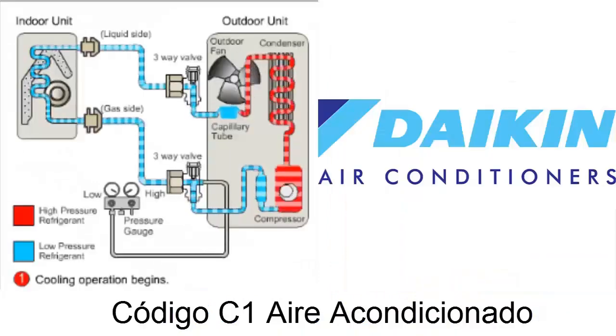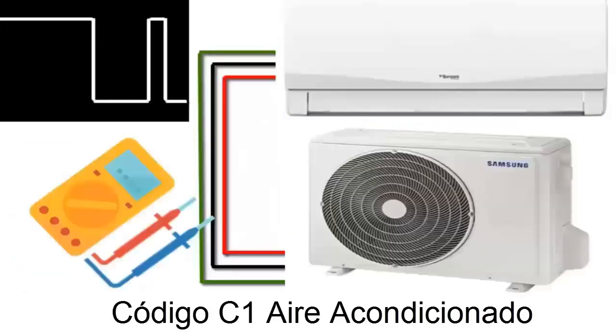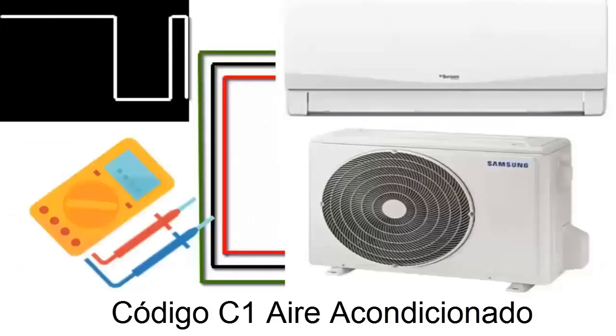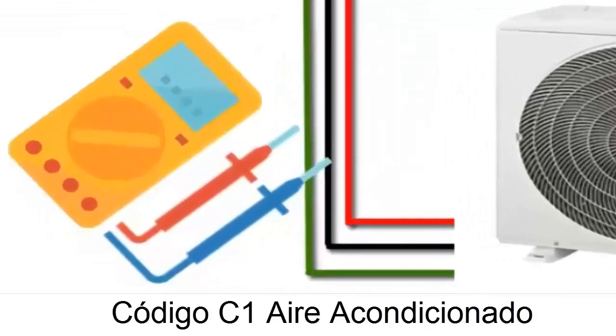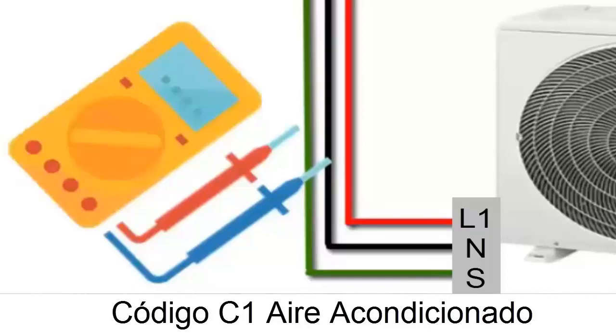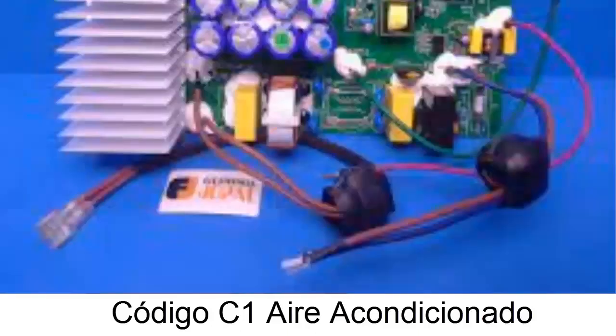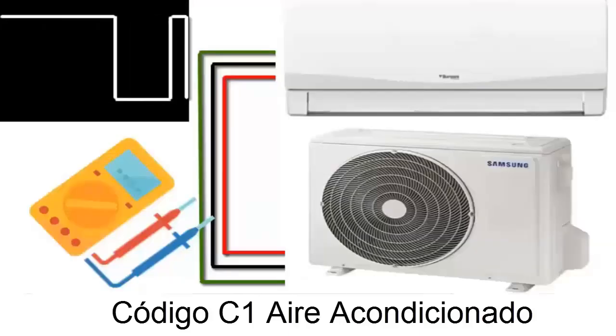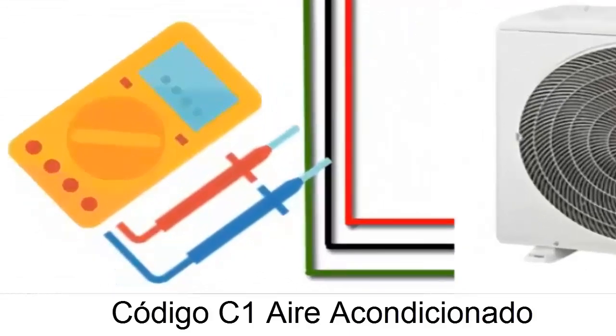In Daikin air conditioning systems, the C1 error code is generally related to communication problems between the indoor unit and another system unit, such as an outdoor unit or a central control unit. Possible causes of this problem are: 1. Failure in the communication cables. 2. Issues in the control unit. 3. Voltage supply problems from the external source.